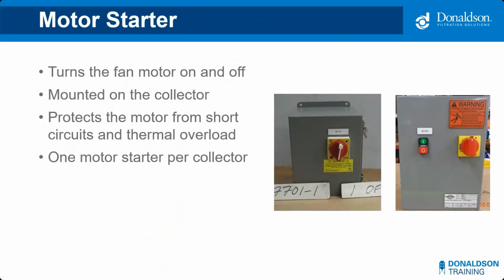If the system you designed uses a collector that uses mechanical separation, you're most likely looking at the most basic type of control, which is a motor starter. I do want to take a second to point out that as we go through this, we're talking about the minimum viable controls that you need to operate each collector. You could have an incredibly advanced control system even for the most simple collector, with remote monitoring, explosion mitigation, and a number of other features you could add, but this is really the minimum.